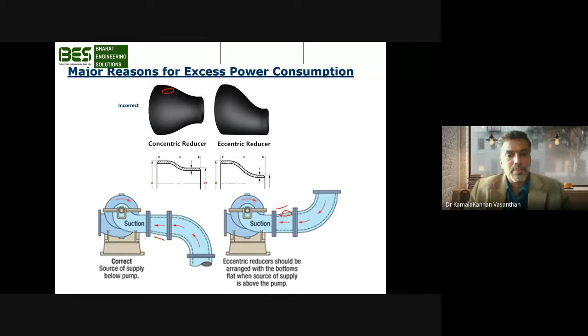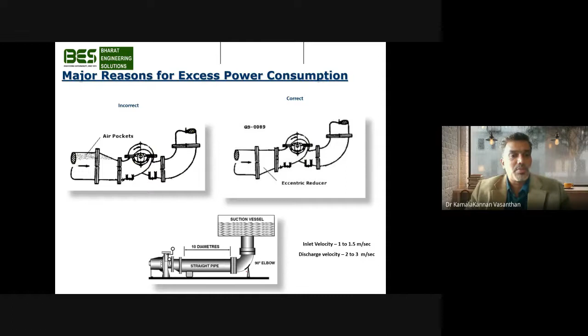Similarly, inlet velocity has to be ensured between 1 to 1.5. This is for pure water, not for wastewater. Wastewater inlet velocity has to differ, and discharge velocity has to be between 2 to 3.5 meters per second. And always ensure there is 10D from that particular section point to the next bend.